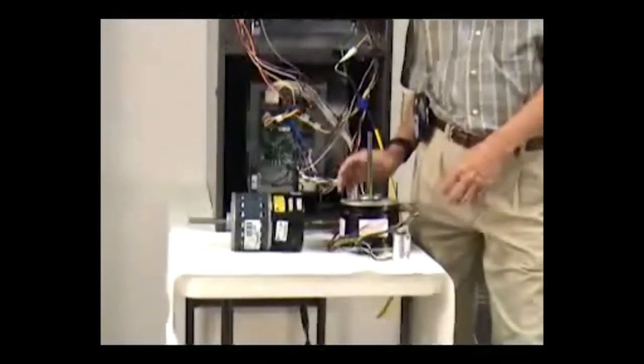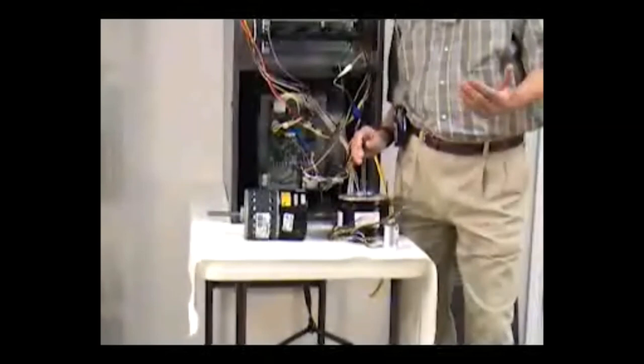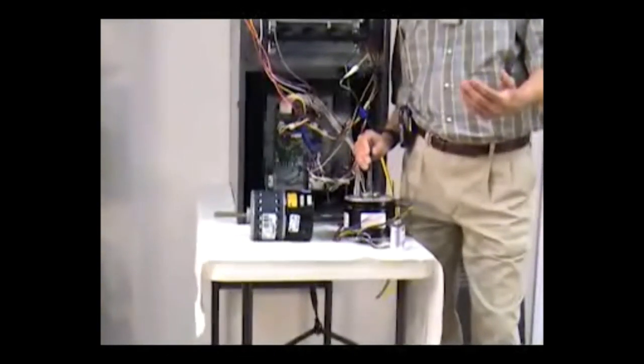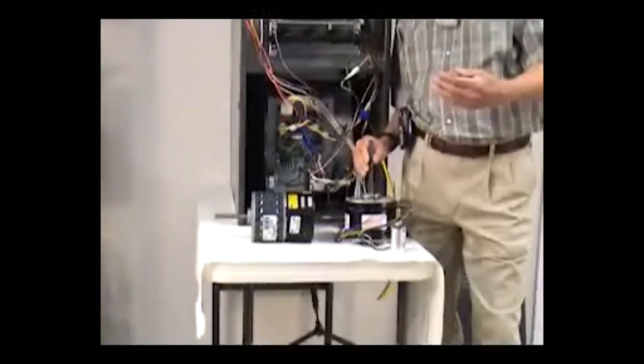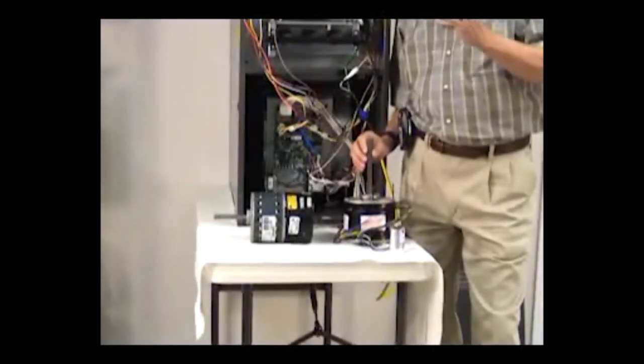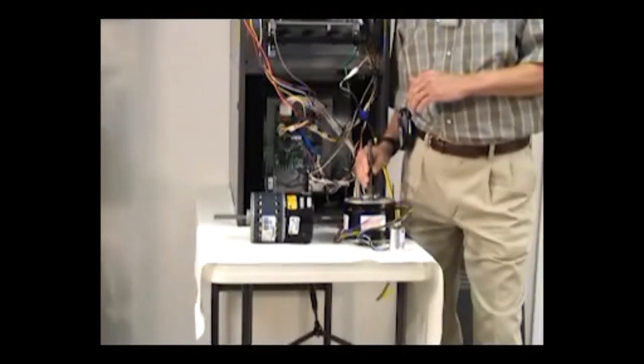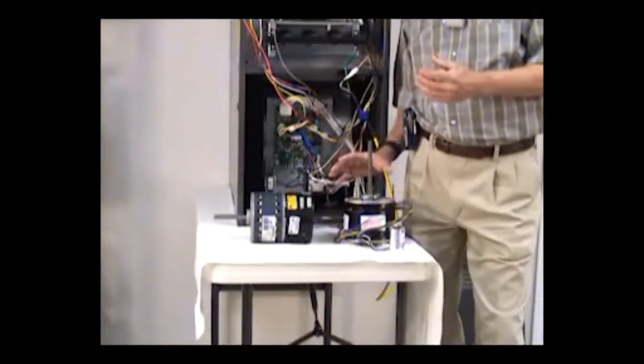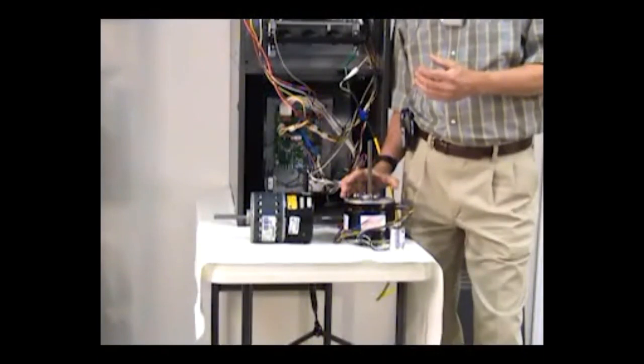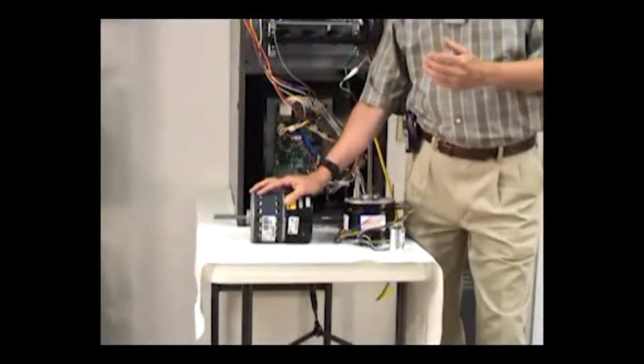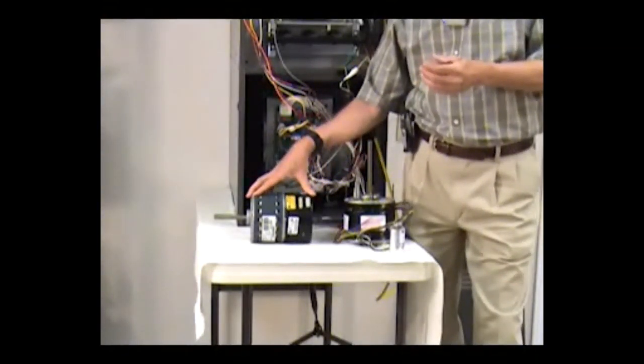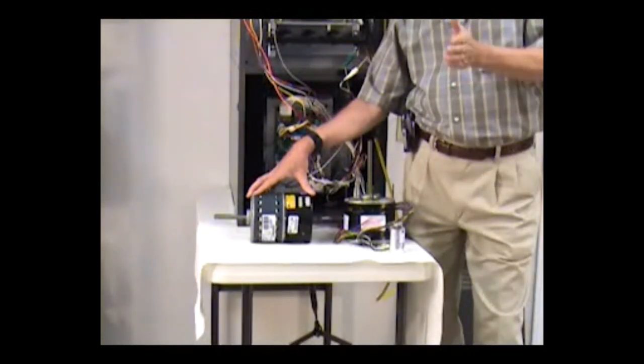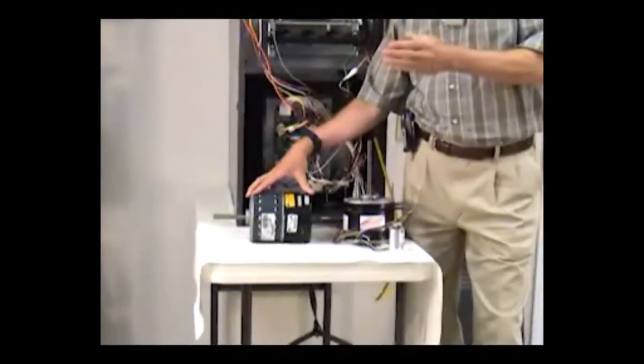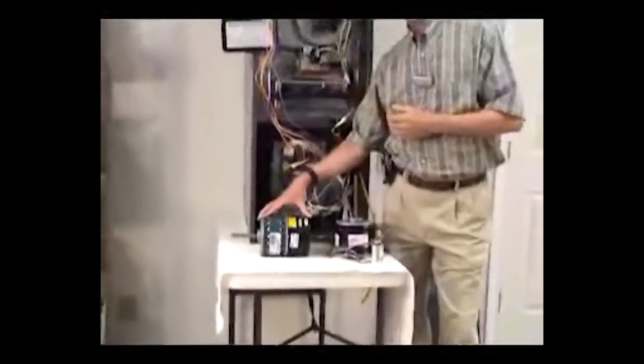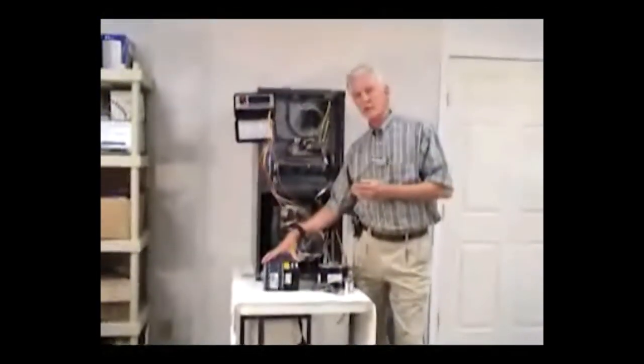voltage applied only. And we're talking about a motor here that when we add a load to it, or we have greater external static pressures, the amperage will drop slightly, but what happens is the curve on the motor will go down dramatically. As we increase above 0.5, then we will see much, much less delivery as far as CFM. Advantage here is that we can go from zero to almost a full inch of external static pressure and maintain the same CFM range, but what happens there is amperage draw goes from a lower amperage at lower external static pressures to a higher amperage draw at the higher external static pressures.